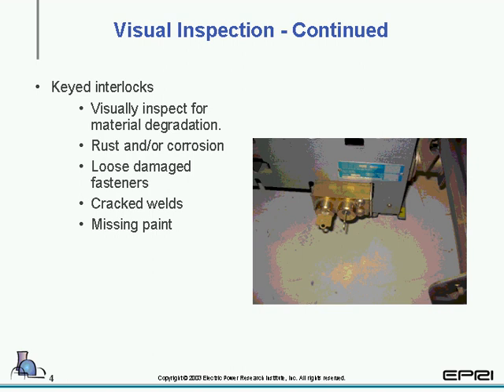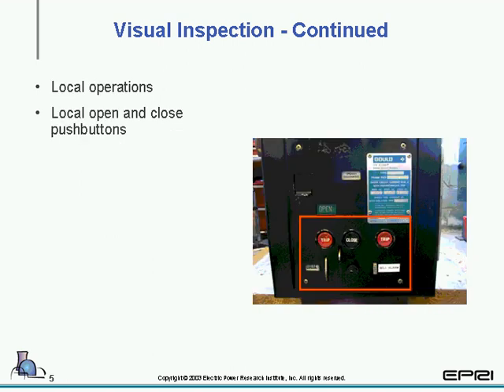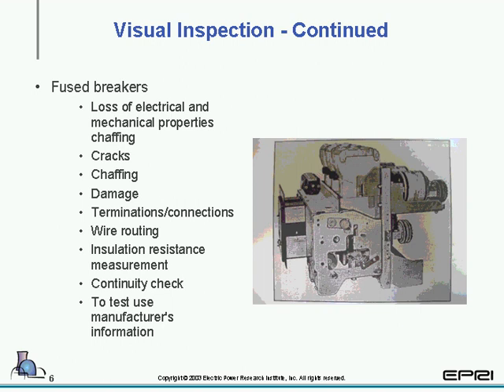All right. The next item we'll take a look at is the Kirk or keyed interlocks. One of the most common is the manufacturer Kirk key. And we have a list of items, as well as verifying that the interlocks work correctly. We have local operation, and some of the secondary wirings may not be the same for your local as for when the breaker is installed in the cubicle. So it's sometimes important to check the operation of these when it's on the bench. Fused breakers. We have a list of items to look at for fused breakers, and we'll be talking more later about how to test the fuses and the fuse indicators.